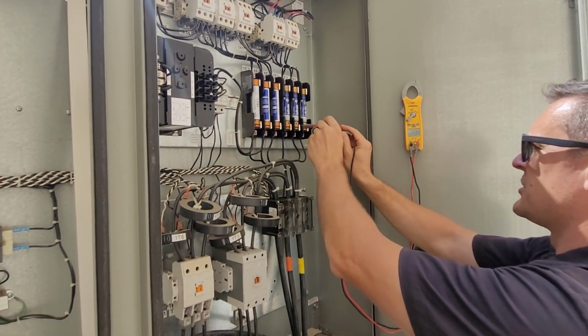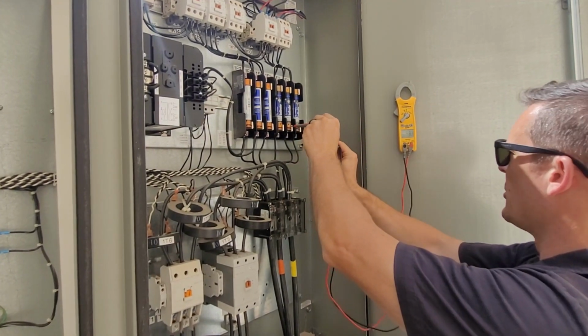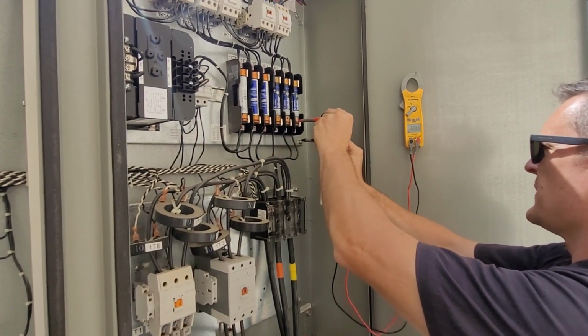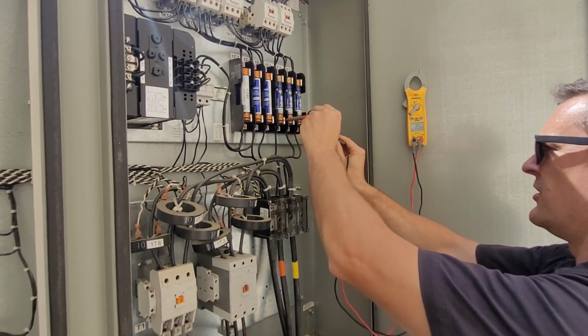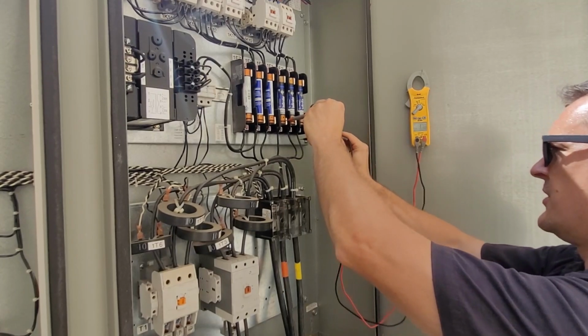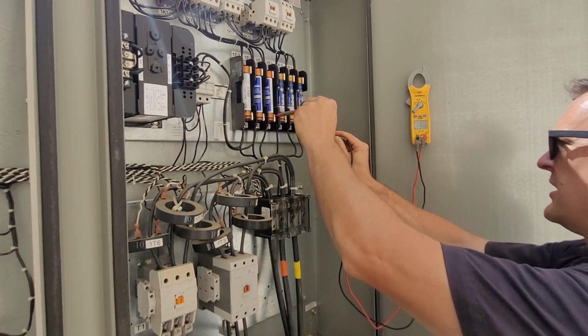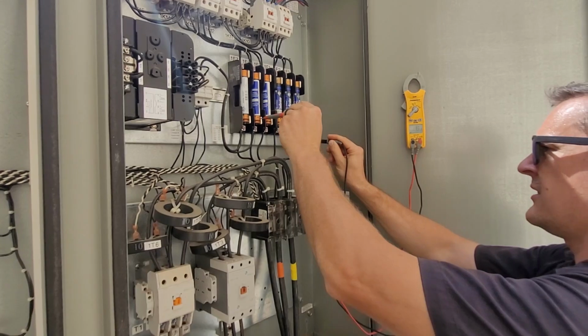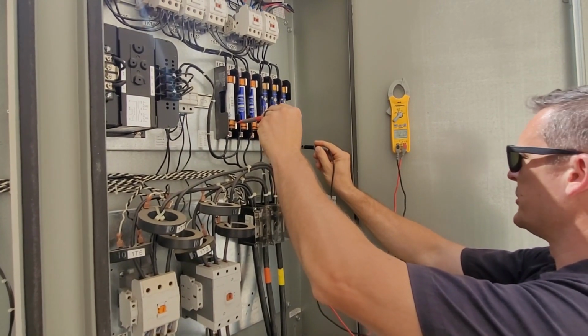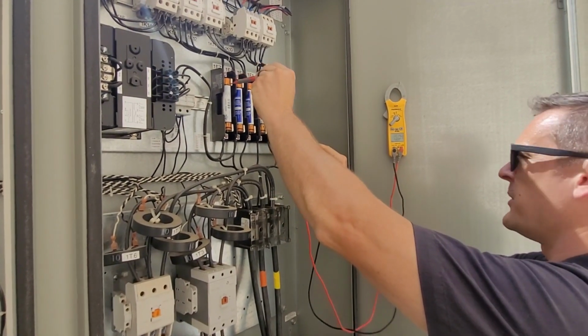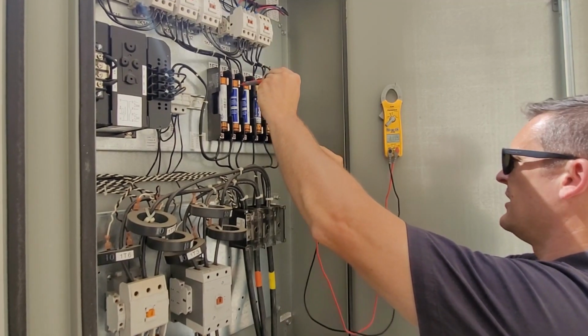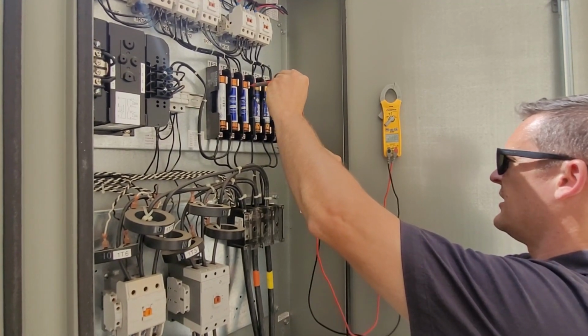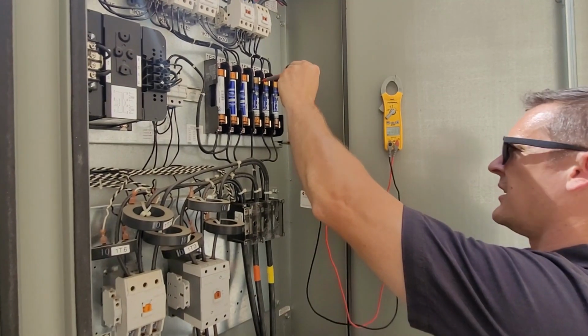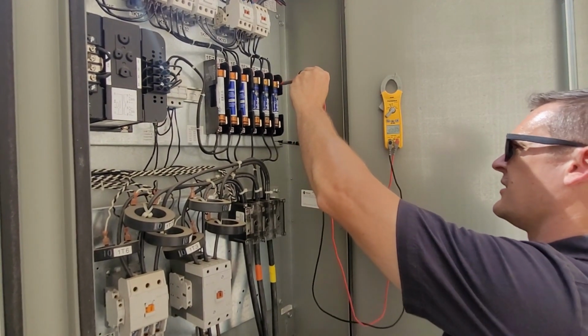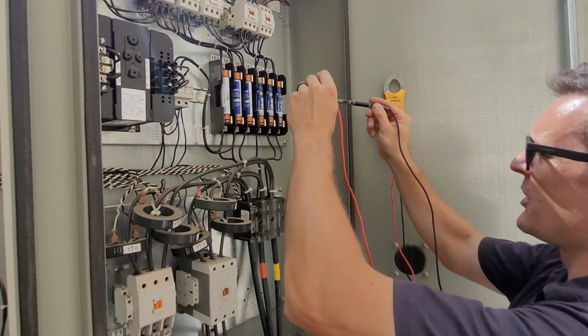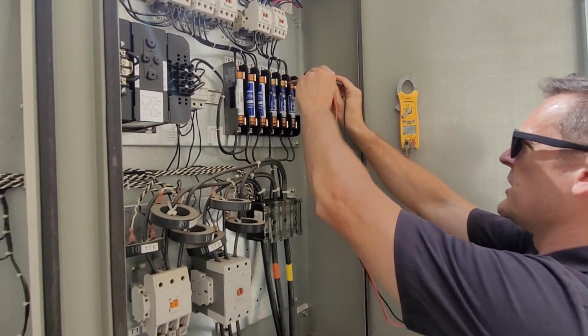So I went between the two. You could do it several ways. You could go to ground and you'll get 280. So we're just checking it coming in and we know they're good on the ground or on the bottom side, on the feeder side. 280, 280, everything's 280. So plenty of voltage coming in. Now you can check them up here. 280, 280, 280, everything's good. 280, 280, 280, and then an even better way to do it is to check between them.